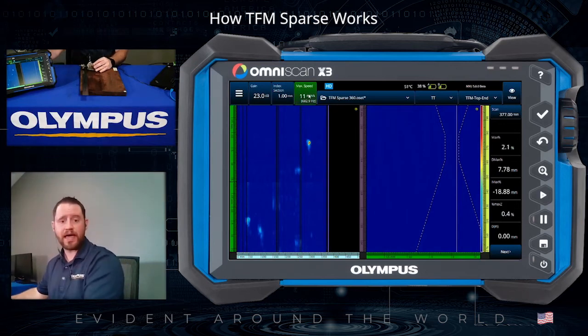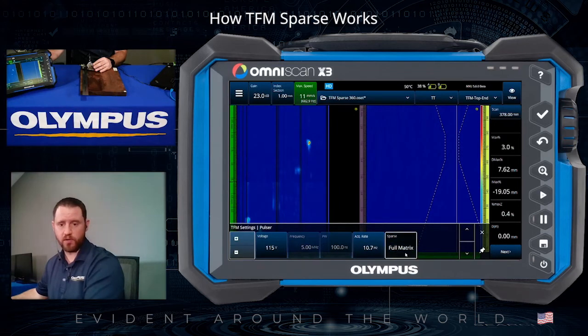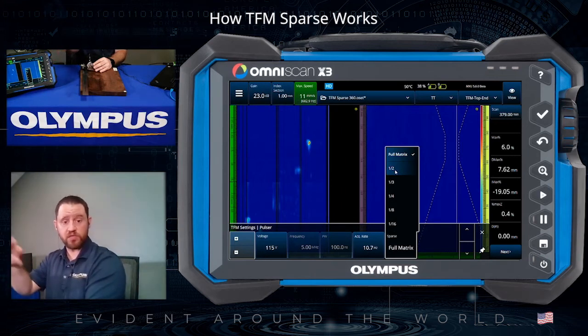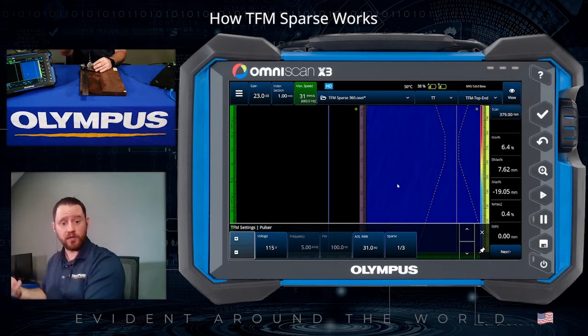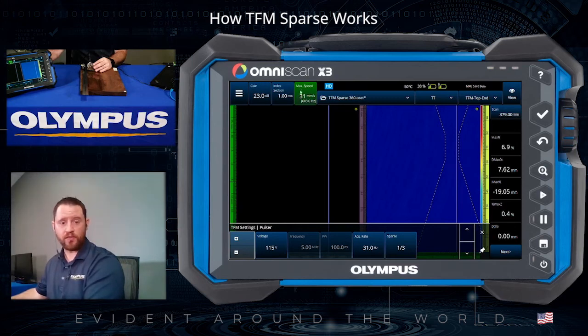What we'll do now is activate the sparse setting and compare what that looks like. In our TFM settings under Pulser configuration is where we find sparse mode. Right now it's running full matrix, but we have flexibility to apply different levels of sparse firing: 1x2, 1x3, 1x4, 8, and 16. Setting it to 1x3 means it skips two elements and fires every third element of the transducer. As soon as it finishes adjusting to 1x3 sparse, we get a significant increase in acquisition rate — now collecting at 31 millimeters per second, up from 11, which is a significant jump.